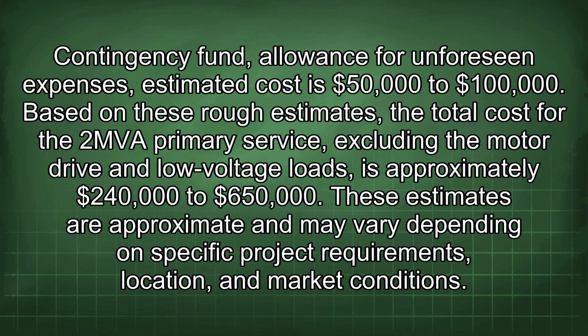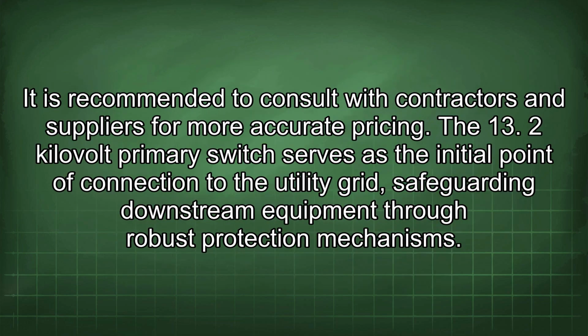Based on these rough estimates, the total cost for the 2 MVA primary service, excluding the motor drive and low voltage loads, is approximately $240,000 to $650,000. These estimates are approximate and may vary depending on specific project requirements, location, and market conditions. It is recommended to consult with contractors and suppliers for more accurate pricing.